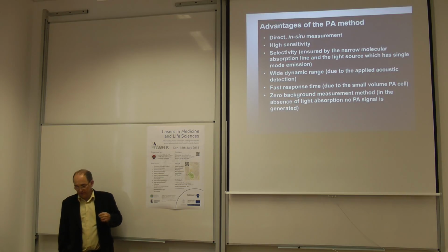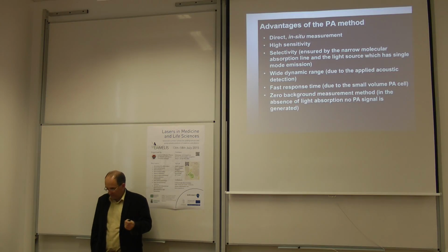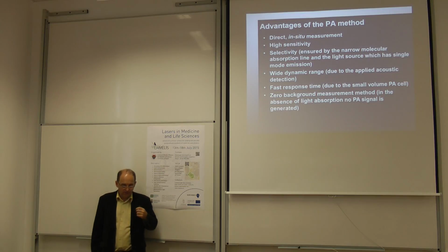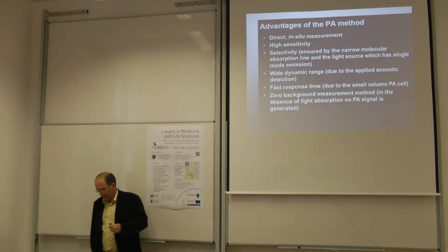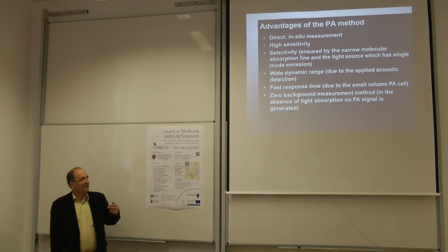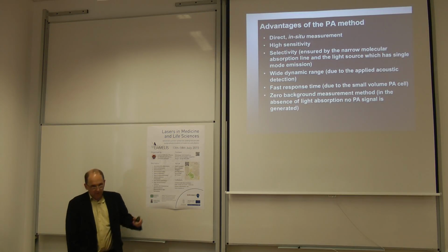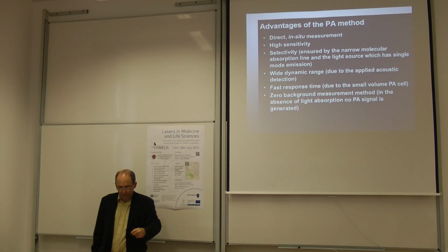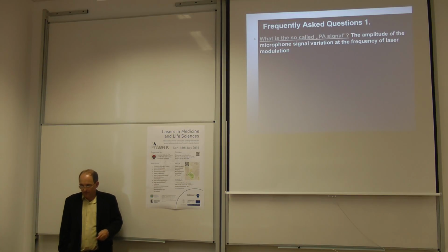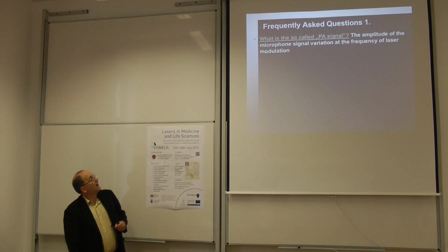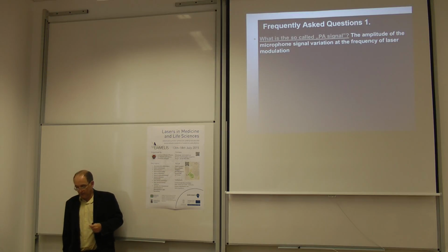It's very important that this is a zero background measurement method, which means that if you do not have light absorption, then no photoacoustic signal is generated. It's a big advantage that no measured component means zero signal. So there are frequently asked questions about the photoacoustic method.